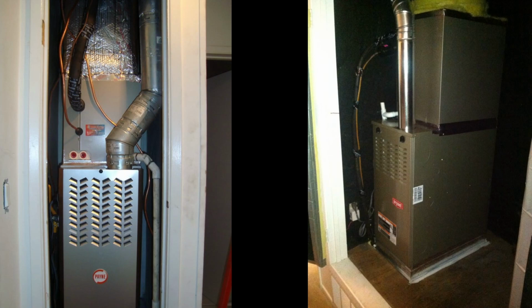If you notice the Armaflex that I've talked about in other videos, that covers your suction side because that side is cold. That's the side that is going out. It's cold, it sweats, it drips water, it can get all over everything. And plus you need to maintain that cool surrounding the suction line, and you don't want that to dissipate. It can change how the operation of your heating and air conditioning system works in the cool mode, not in the heat mode.